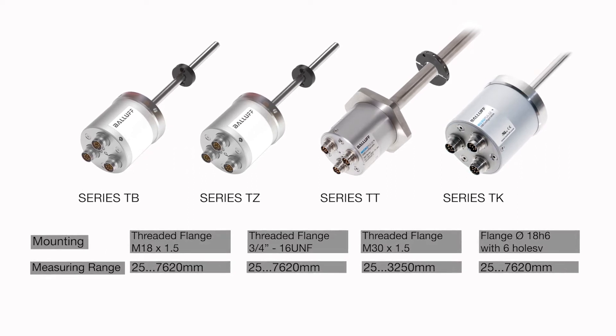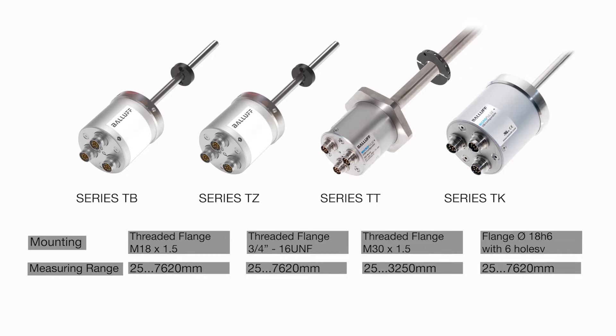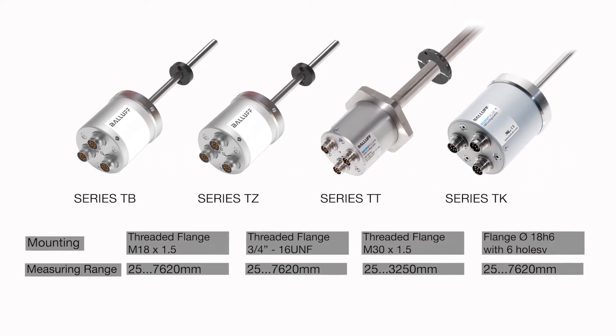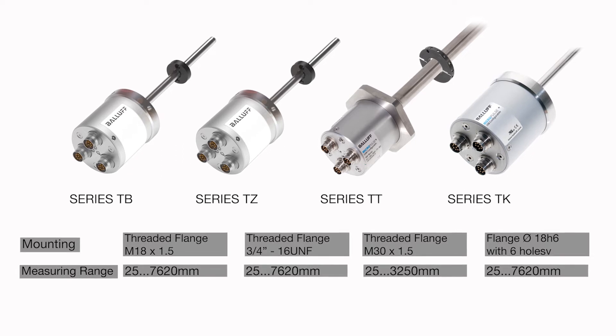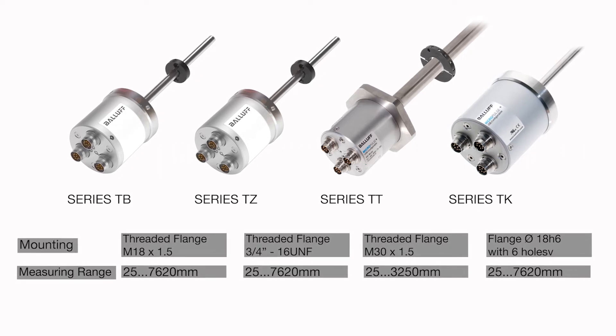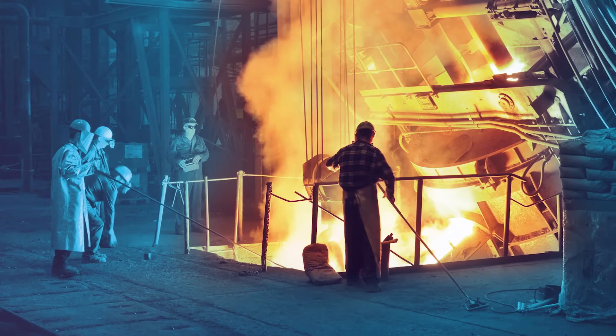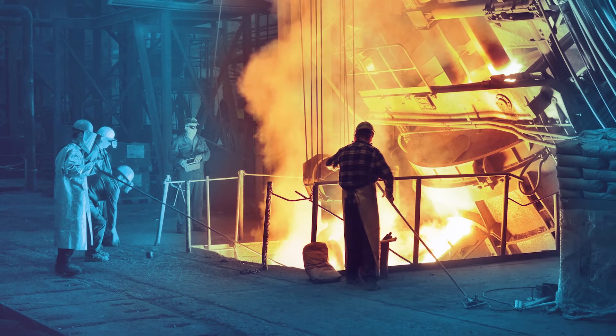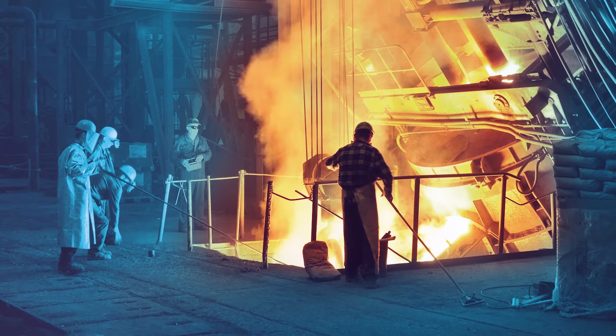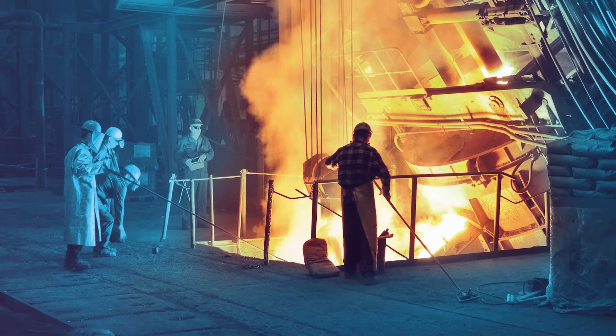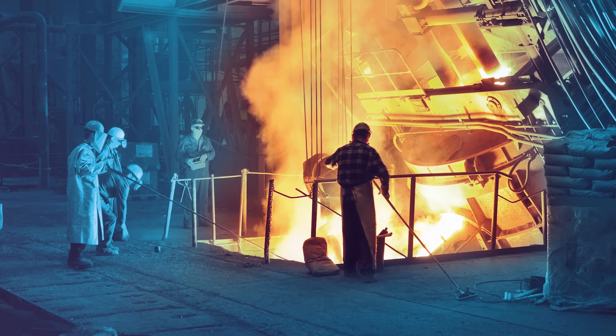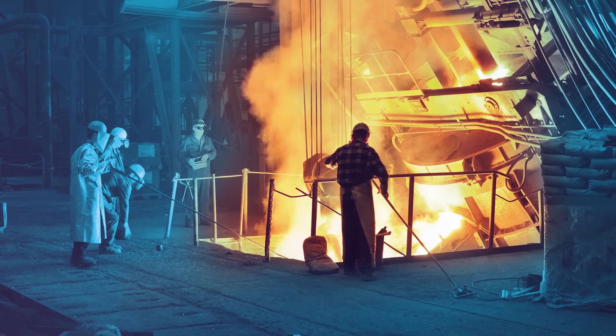These rod-style transducers have either two or three separate sets of electronics and sensing elements operating concurrently in one housing. This ensures uninterrupted processing and provides insurance for uptime-critical applications, where downtime isn't only costly but potentially catastrophic. For example, monitoring a hydraulic cylinder pouring molten steel in the steel manufacturing industry.